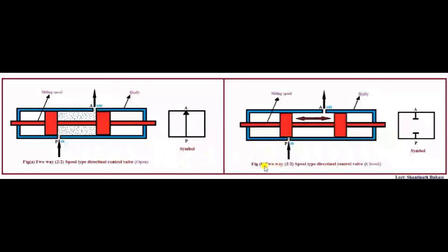Now we will discuss about case 2. From figure B, after the spool gets actuated or moved horizontally with the help of push buttons or any solenoids, the spool will move and block the inlet port P so that fluid will not enter into the valve. In this symbol, port P and port A are blocked — fluid from P will not enter into port A because the spool is blocking the way.